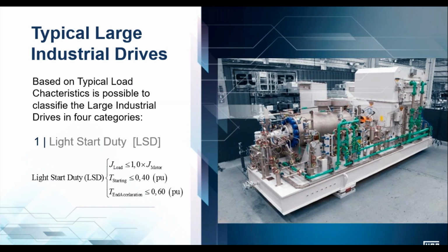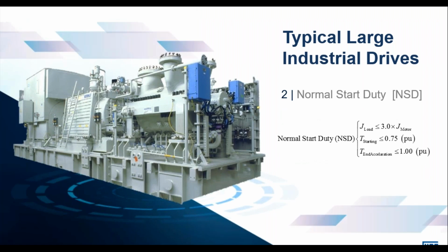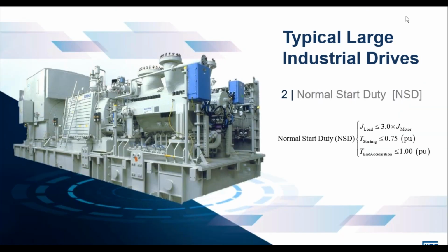So we've defined here light starting duty as an application where the load inertia is less than or equal to the motor's inertia, that's essentially the motor rotor inertia, where the starting torque required by the load is less than or equal to 40% or 0.4 per unit value of the nominal rating of the motor, and where you have an end of acceleration load torque of 60% or less of the motor's nominal rated condition. Then we define a normal start duty scenario. We define a normal start duty for the purpose of this presentation and this discussion as load inertia less than or equal to 3 times the motor's inertia, starting torque required to get the load away of 75% of the nominal rating, and end of acceleration torque of less than or equal to 100% of the nominal rating.